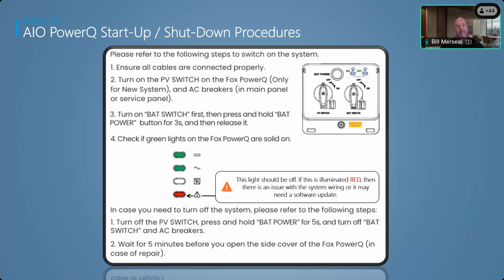So it shuts the power off at the inverter. Just so you know, the wires going to your solar system are going to be hot—that PV switch only turns the power off at the inverter. So don't think your PV lines are dead when you turn that switch off; it's really just for the inverter. I just want to make sure you guys know that.